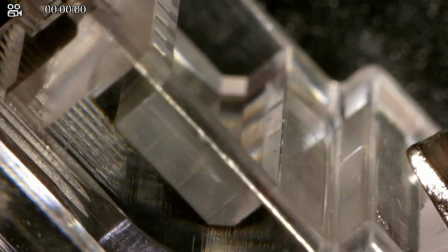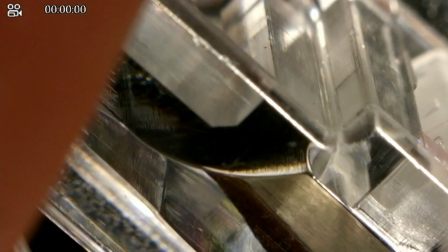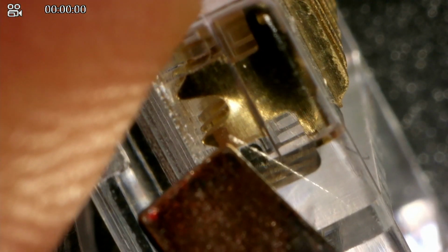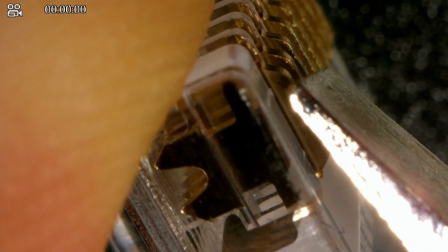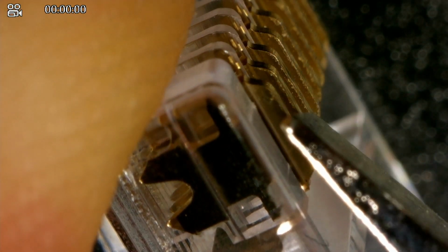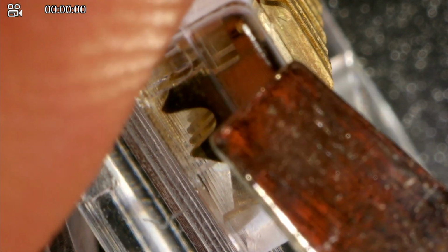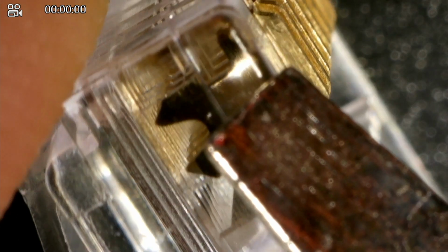What we're going to do is we're going to insert the conductors right from the back of this jack, and each conductor is going to go in its own groove, which is going to be underneath the connector here. Now when we crimp this jack, those prongs are going to come down, and this connector is going to pinch the insulation and make a connection with the bare copper that's inside the insulation.